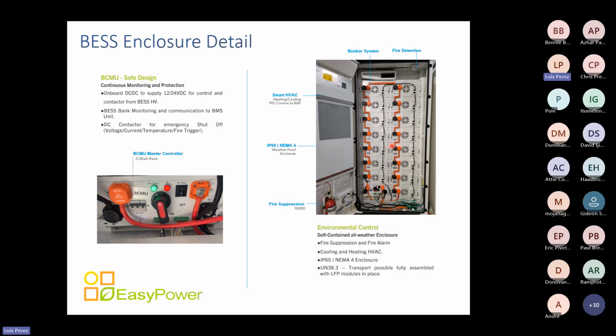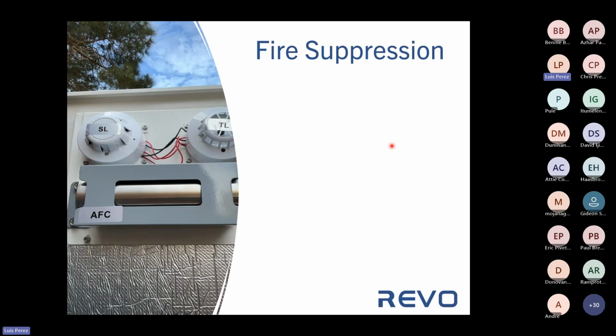The second important point is risk. It's a risk-reward equation, and one lithium fire is one too many. As you'll see in international news, once these fires start, they're very difficult, if not impossible, to stop, from small systems to very large ones. There was a very bad lithium fire in the US a couple of weeks ago at a utility-scale storage location. In our units, we use a condensed aerosol fire extinguishing system.